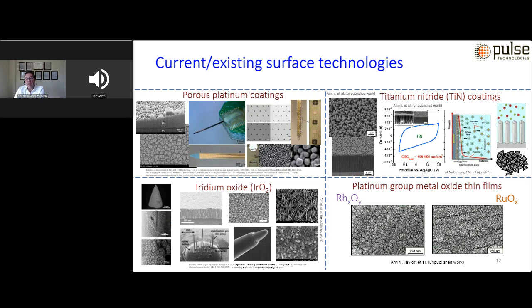Platinum black has been used for a number of years and is still being pursued. It is essentially a nanoporous platinum coating that has very high surface area and, as a result, high electrochemical performance, but it has very low and poor durability. Titanium nitride has been widely used. It is a chemically stable metallic conductor with excellent biocompatibility and excellent electrochemical performance, and has been used widely for many cardiac rhythm management devices.